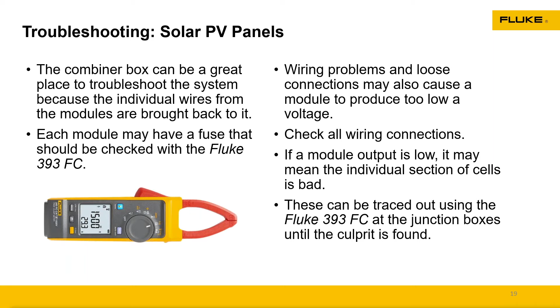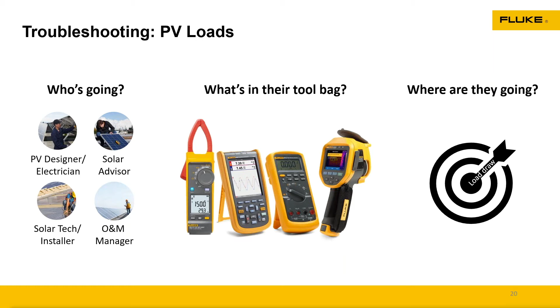So let's look at the loads. Again, this is coming off of your PV system, all of your back to the combiner box, and this could be going even to your inverter. Again, who's doing all of this? Every one of the personas that we talked about earlier. What's in their tool bag? They're looking at the voltage, the current. You might need a scope meter to look at the output of the AC side of your inverter, a DMM, and again, a thermal imager. Thermal imagers are huge in this environment, as we can look for hot spots either on the panels themselves, at the combiner boxes, or at the inverter.